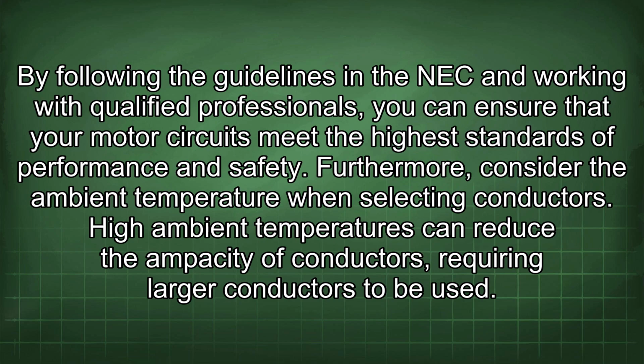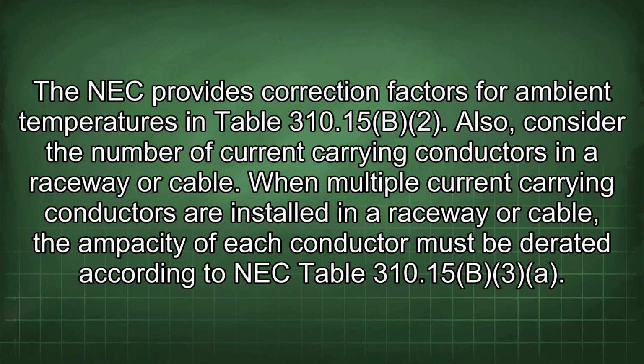Furthermore, consider the ambient temperature when selecting conductors. High ambient temperatures can reduce the ampacity of conductors, requiring larger conductors to be used. The NEC provides correction factors for ambient temperatures in Table 310.15(B)(2). Also, consider the number of current-carrying conductors in a raceway or cable.